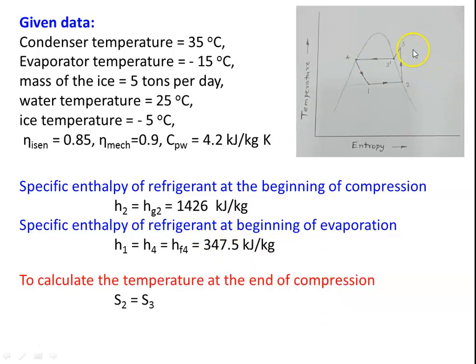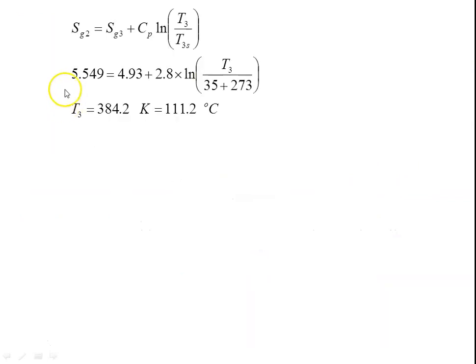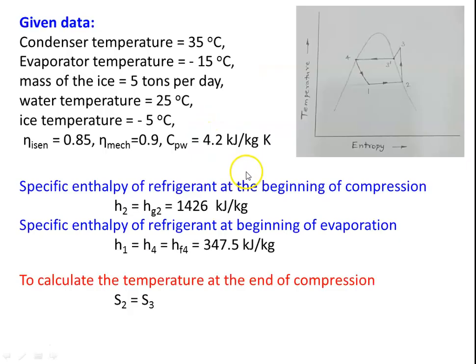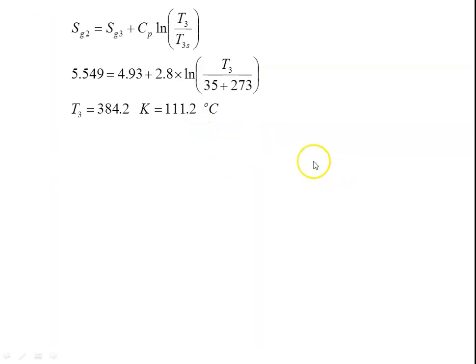To find superheated vapor temperature at end of compression, using S2 equals S3 (isentropic). S2 equals SG2 equals SG3 plus Cp·ln(T3/T3s). Substituting: 5.549 equals 4.93 plus 2.8 into ln(T3/(35 + 273)). Solving gives T3 equals 384.2 Kelvin, or 111.2 degrees Celsius. This is the discharge temperature from the compressor.